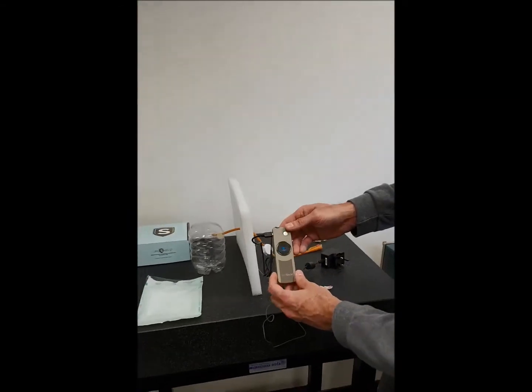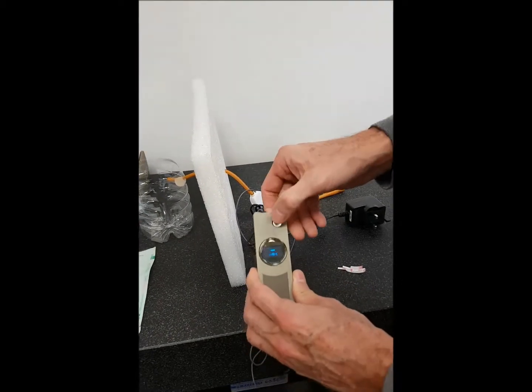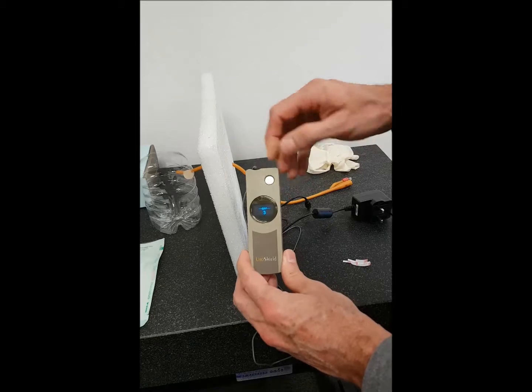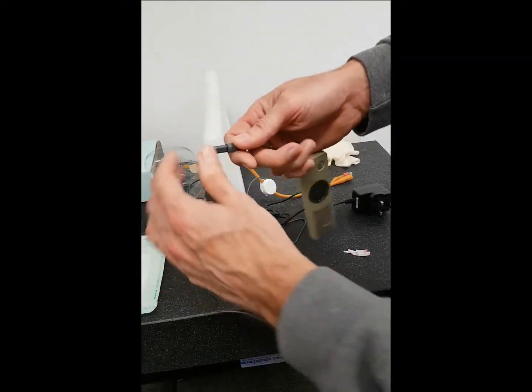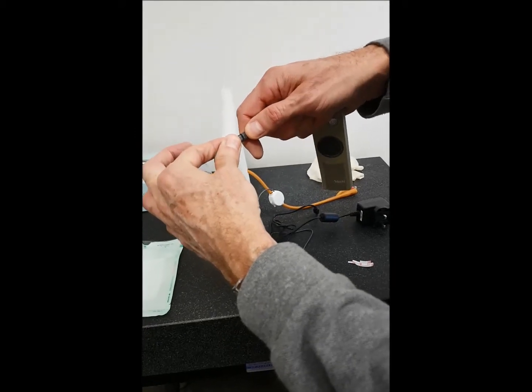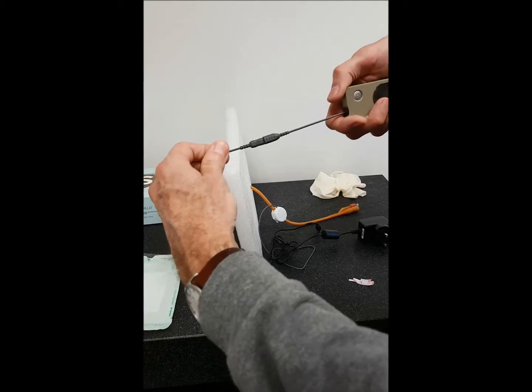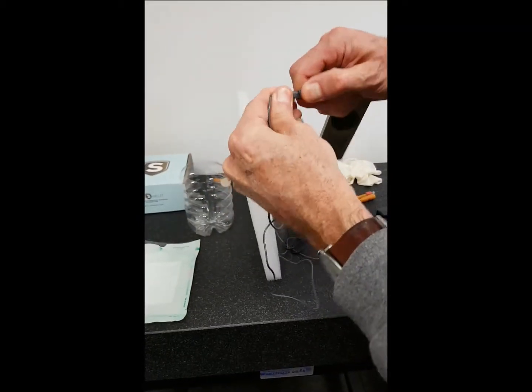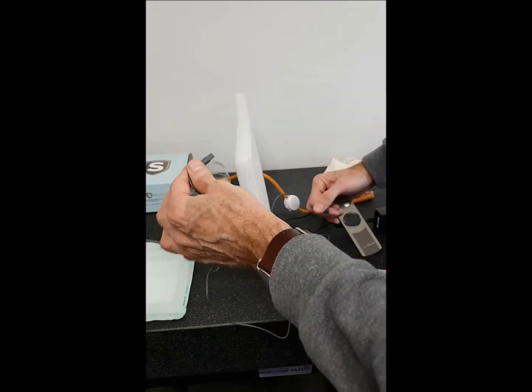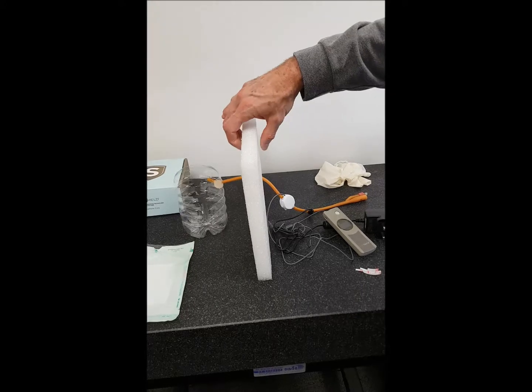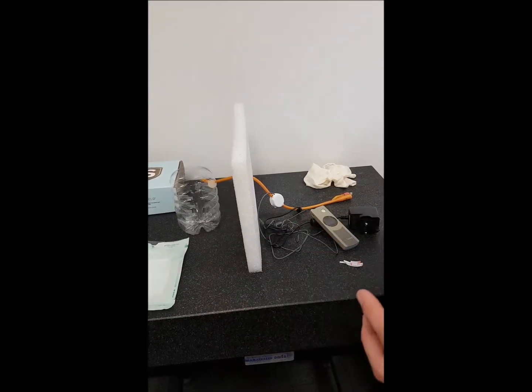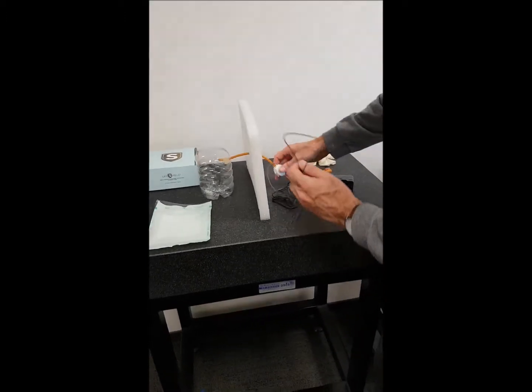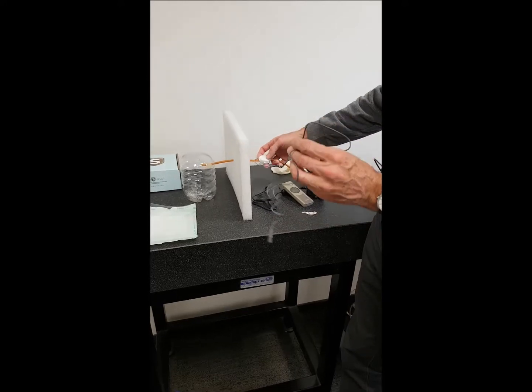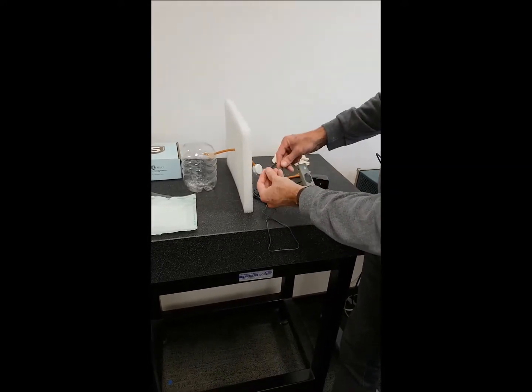Cleaning the patient. The UroShield driver is not waterproof and should not be exposed to water. Before cleaning the patient, you have to disconnect the unit by turning it off by pushing the on-off button. Then pull on both sides of these connectors to disconnect it. Do not pull it against the unit, but between those two connectors. After disconnecting it, you can go on with the patient cleaning, and after cleaning is finished, the actuator and wire should be dried using a towel, then reconnected and reactivated.